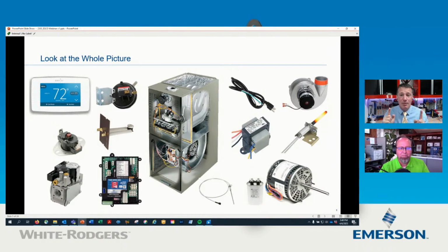A very common thing that happens on Goodman furnaces, and it gets overlooked by a lot of technicians, is that when we leave our transformer and have that 24 volts coming into our control board, a lot of times on a Goodman the limits are before the thermostat connections, before the R connections on the control board. So there is another little loop of limits that comes out and then goes back into the control board immediately. And another brand of furnace may not have that.